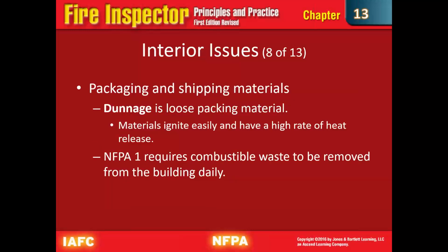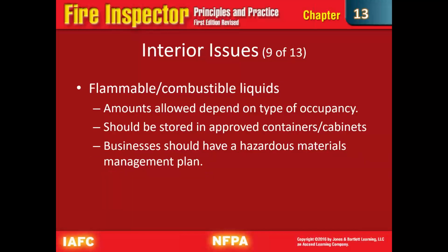Packing, shipping materials. Dunnage is loose packing material. They ignite pretty easily, have a high rate of heat release, and NFPA 1 requires in the code set that combustible waste be removed daily from buildings. IFC has a very similar code that covers that.